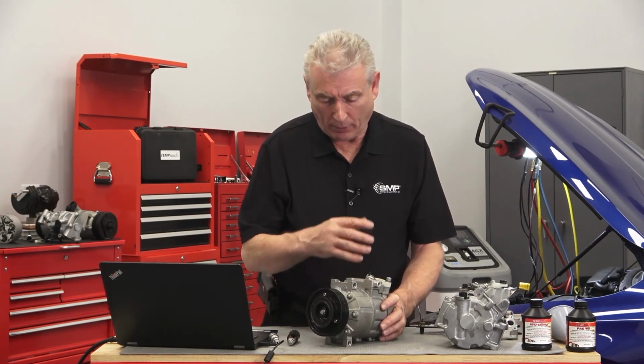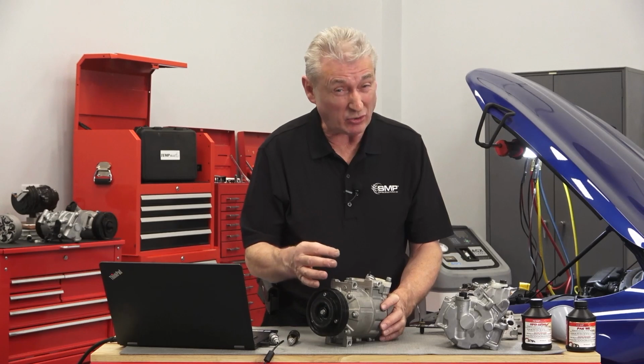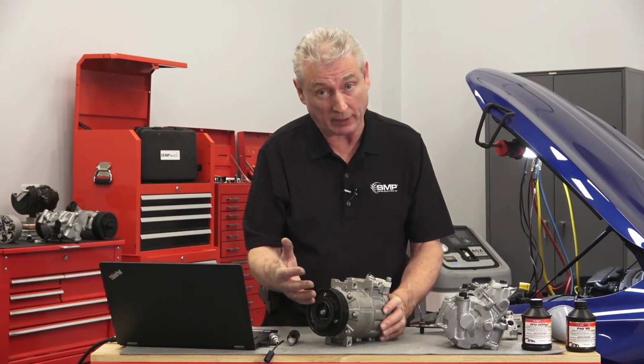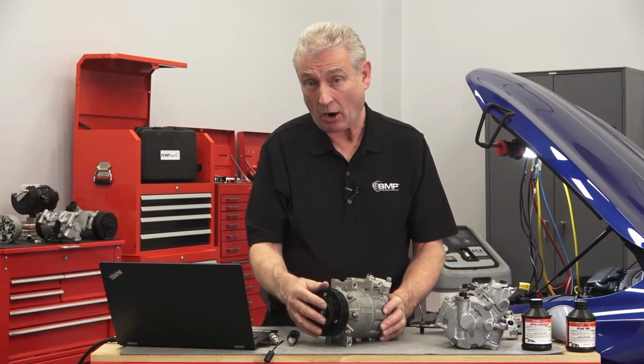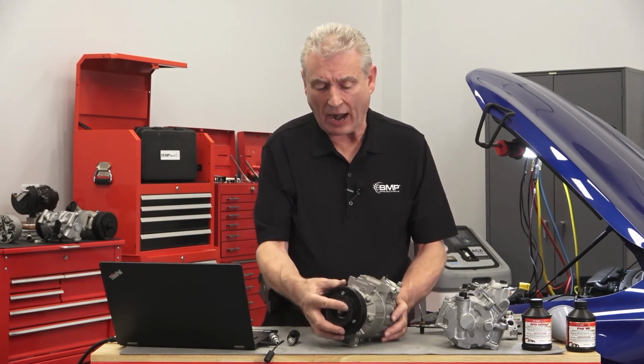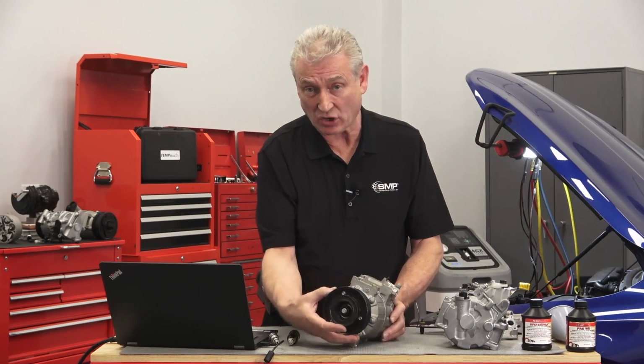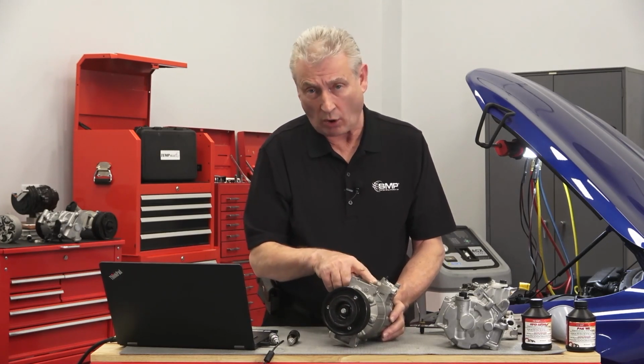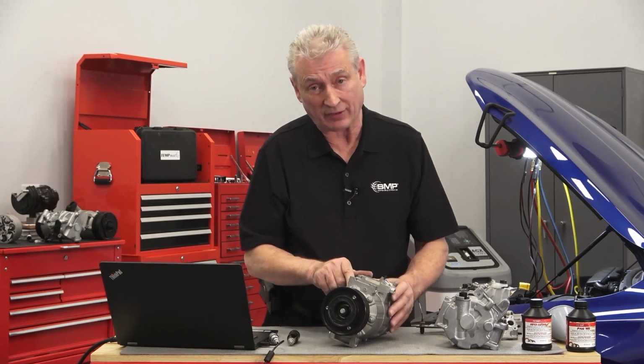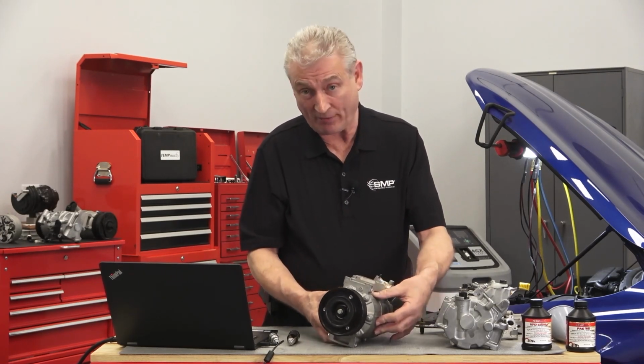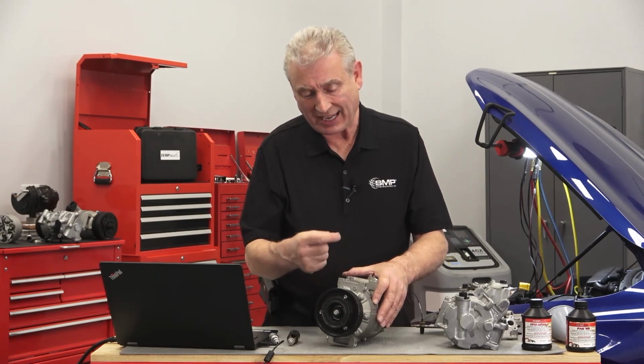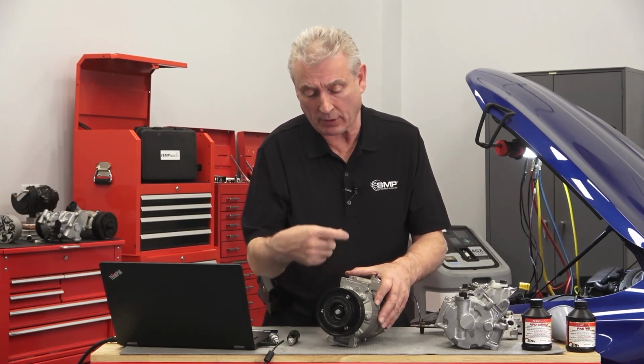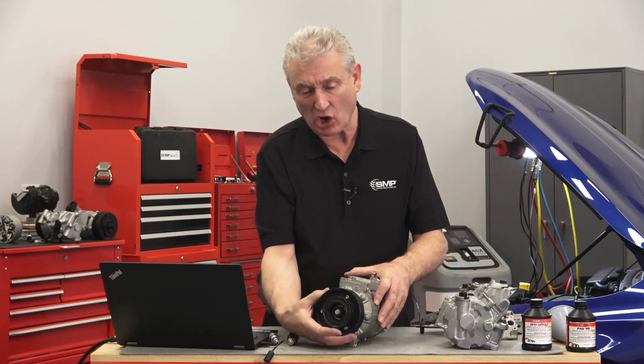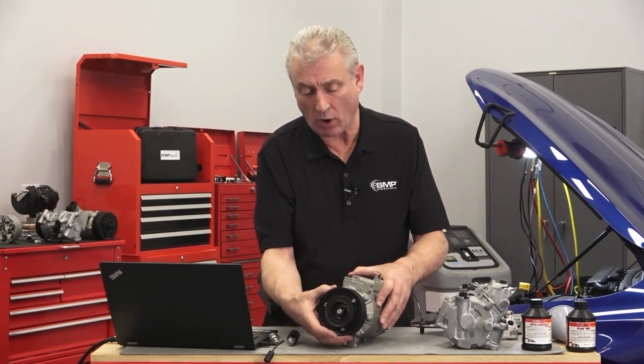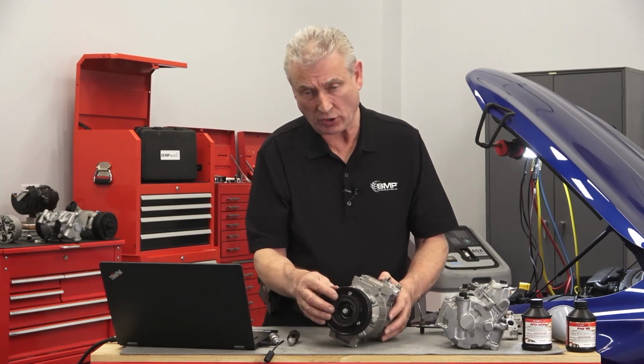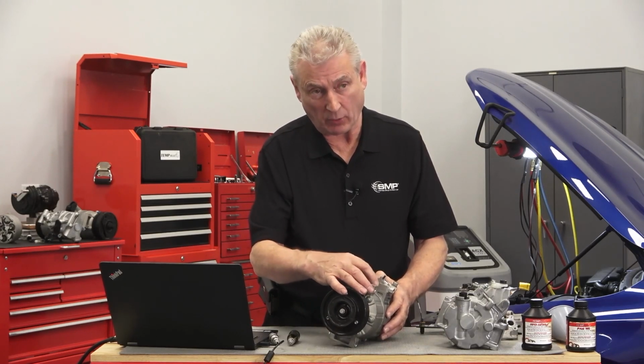It's very important if you're putting an engine in a vehicle or doing a motor swap, or maybe somebody's doing some body work on the system and the refrigerant has leaked out because the condenser was leaking, or maybe somebody's recovered the refrigerant from the system. Never start the engine or run this compressor with no refrigerant in the system. Even though the compressor may be full of oil, we're depending on the refrigerant to keep the pot stirred, in other words, to agitate the oil and keep all the moving surfaces inside the compressor lubricated. Otherwise, you'll damage the compressor very quickly, very easily.